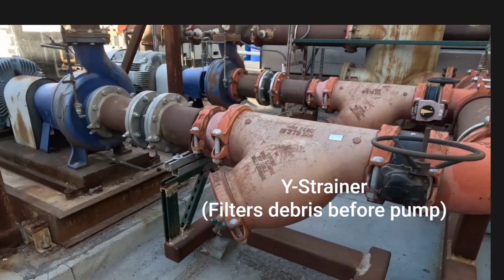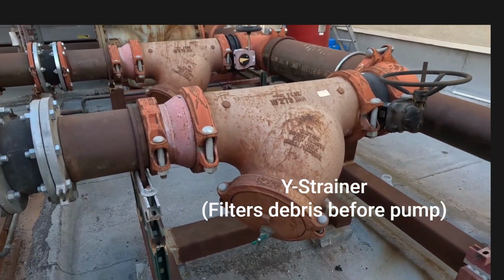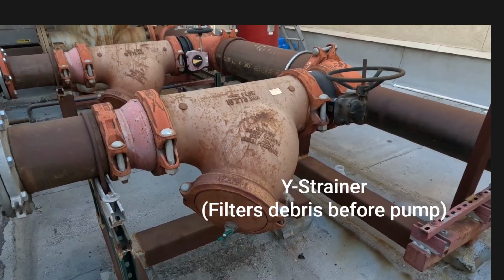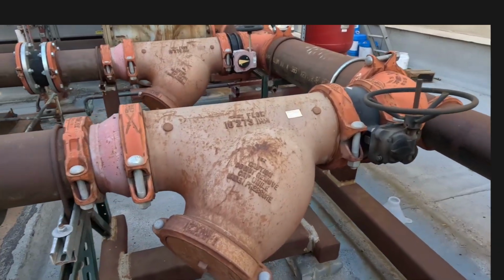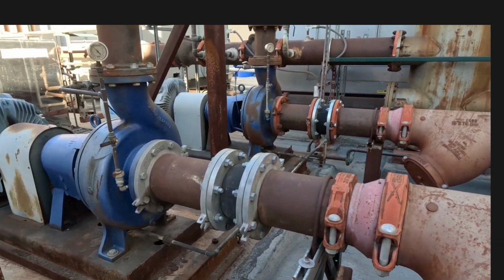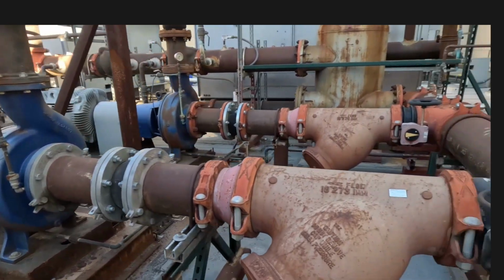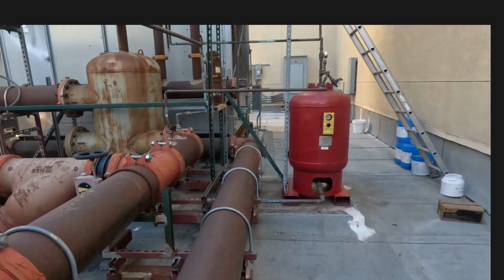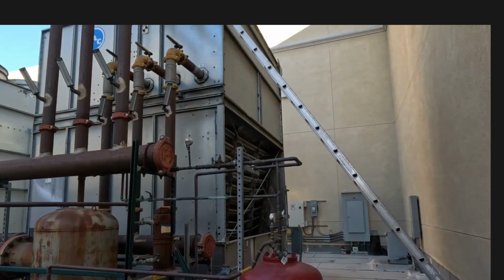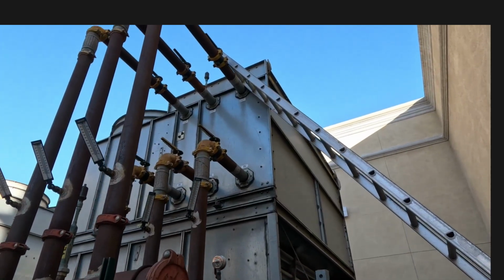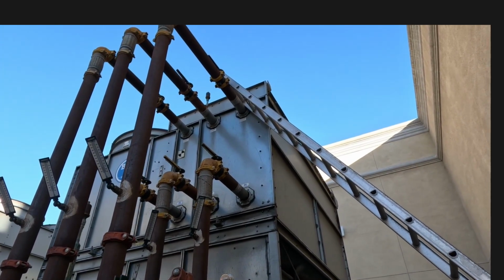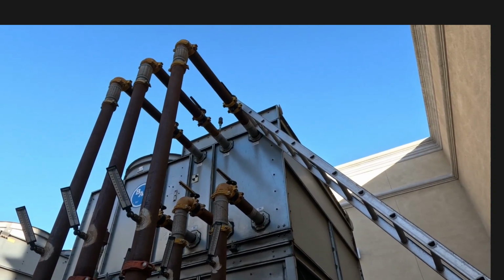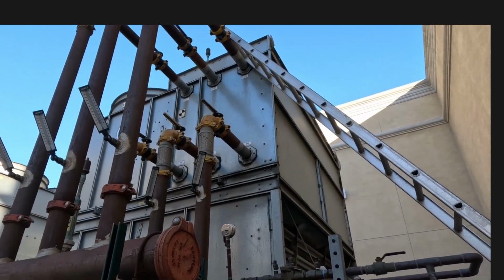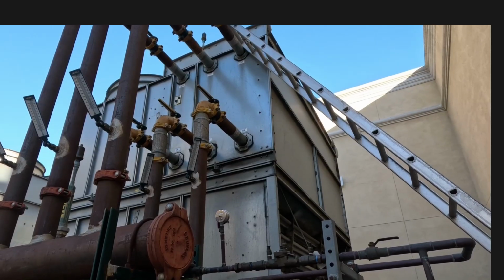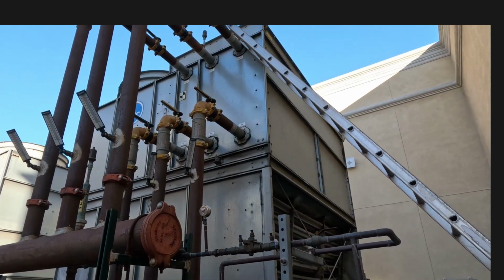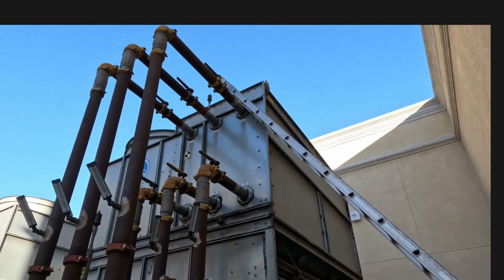This right here is your Y-strainer. So you shut the system down. There's a screen in there that you can pull out, and it's filtering all the water coming back in here before it enters the pump. So as you can see, we got some piping coming in and out of the tower in here. Those top pipes, they're labeled as an out. So that's water leaving in the pipes. They're down there, and there's a label there that says in. So that's entering water. So water, condenser water enters through the bottom and then comes back out of the top.